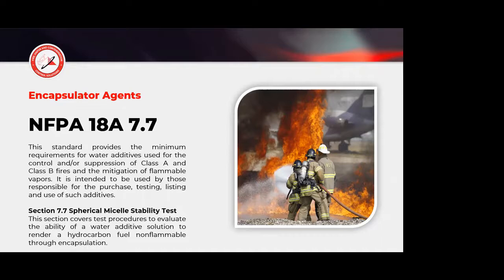I think it's important to start out, when we first started out in 1997, you have a new technology, it's patented, you're bringing it to the market. At that time, there were 2 standards. There was the NFPA 11 standard, which was low, medium, high expansion foam. Well, the F500 encapsulator agent doesn't create bubbles, and our mechanics aren't based on forming bubbles. So we had to list it as a wetting agent for the time being so we could work with the NFPA Standards Council to create a new category of agent. I had put forth that we would make it NFPA 19 encapsulator agents.